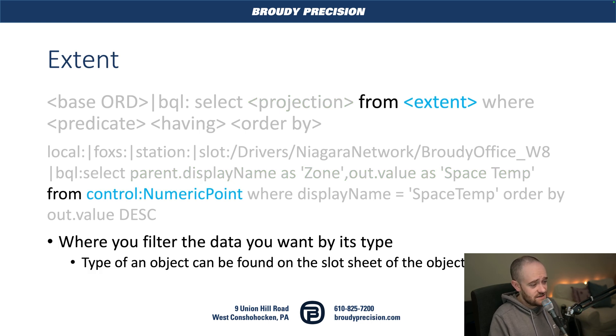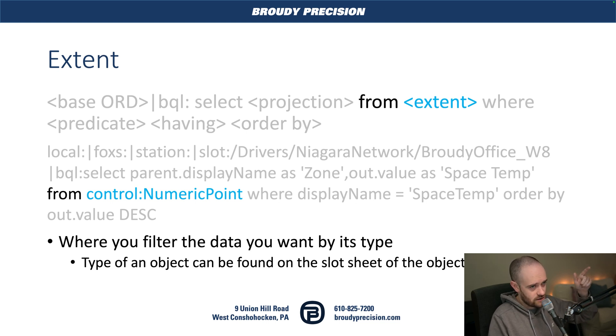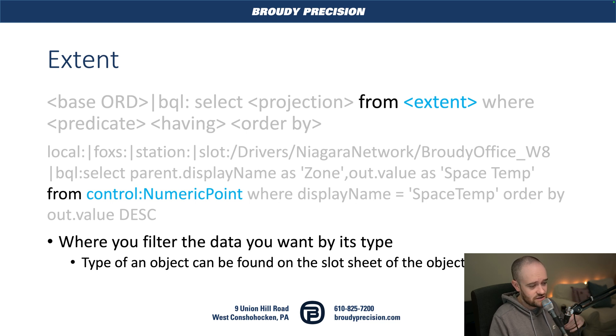Next is the extent. This always starts with "from" — so we're looking at results from objects that are of this type. In this example, we're looking at only objects that are numeric points. This is using the Niagara types. If you don't know what the type of the object is that you're looking for, you can find that type by going to the slot sheet of the object above what you're looking for. So if you're looking for an alarm extension, you would go to the slot sheet of the point that that alarm extension is on, and on that slot sheet you could find the actual type of the alarm extension.